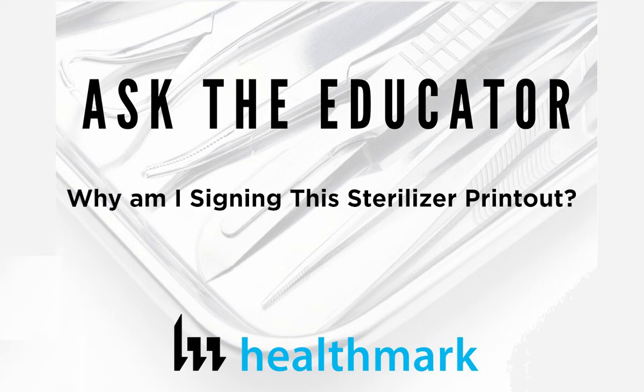So you can put some key bullets on there like, hey, you need to make sure your sterilization cycle, let's say it's set for a 270 4-minute cycle. So at 270, 4 minutes, you want to find out when it first hit the 270 range, look at the time, let's say it was at 14:20, and make sure it held in that 270 range for that 4 minutes. So, steam sterilization, you've got time, temperature, and pressure. Those are our parameters to make sure that our sterilization process happened, right? And so those are the things that we really need to be paying attention to.